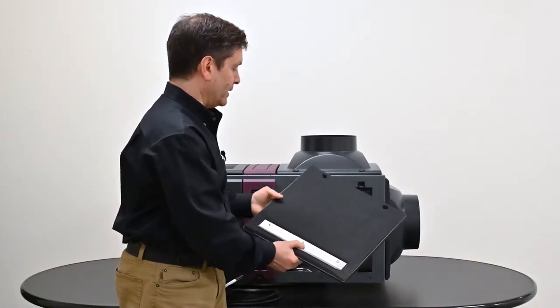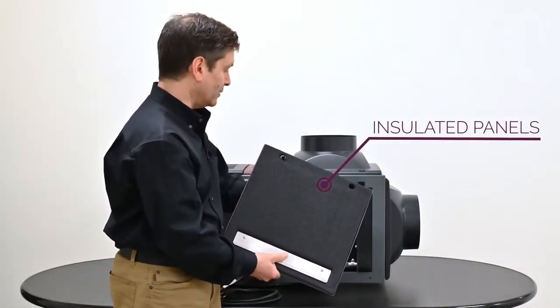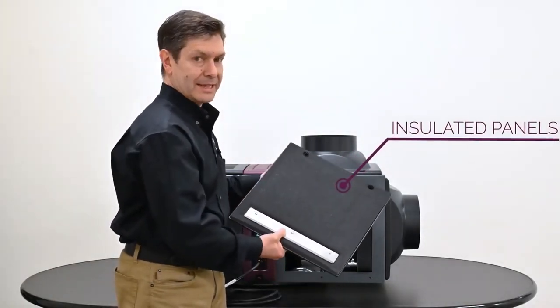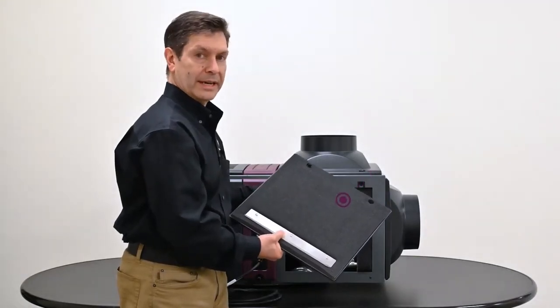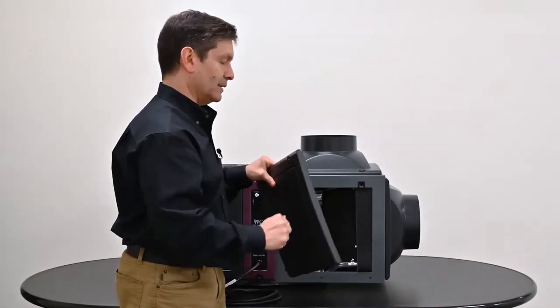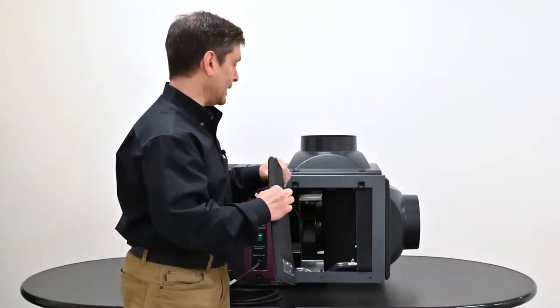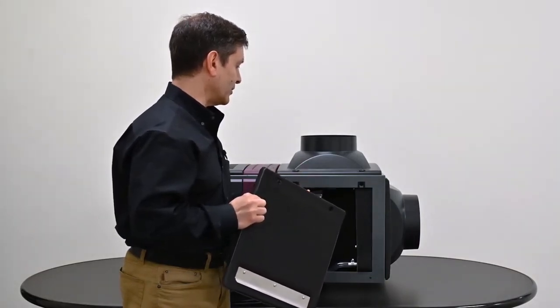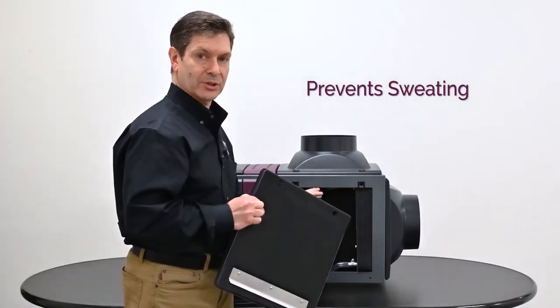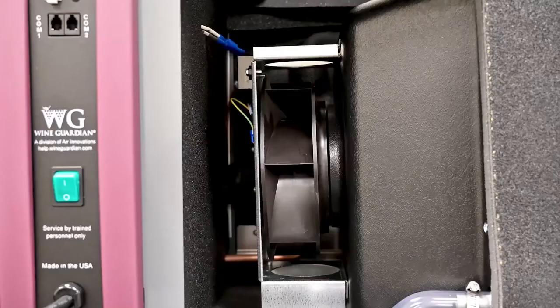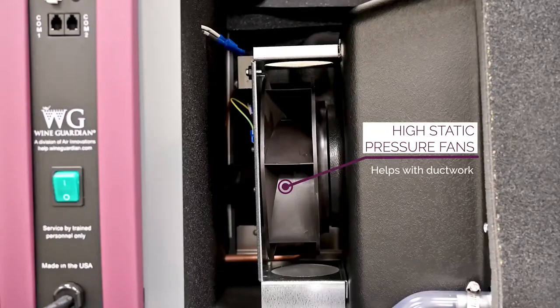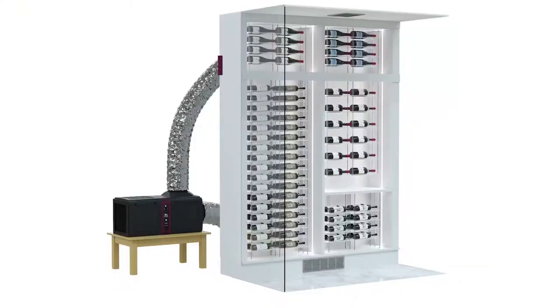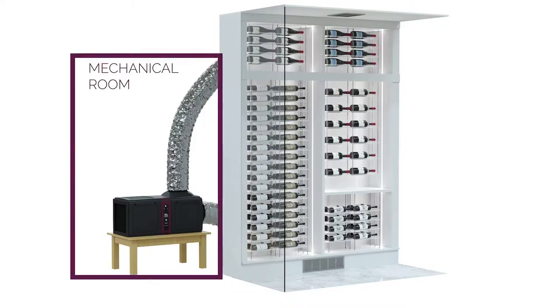You'll see that we've incorporated additional insulation into the panels, as well as the body of the unit itself. This is ideal for protecting against warm areas. A lot of times these units are mounted in a warm mechanical space, an attic, a crawl space, and that extra insulation not only provides a barrier and prevents it from sweating, but it also adds to reduced noise from the system. While we've got the panel off, you'll notice that we've incorporated high static pressure fans. This helps with ductwork connections, extended lengths of ductwork. Generally, we like to see the unit placed in a mechanical room that's relatively close to the wine cellar, usually right next to the wine cellar within a 20-foot range, 20 to 25 feet range.